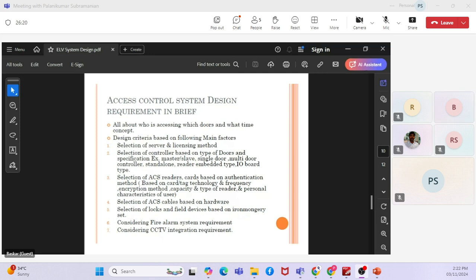So when we are choosing the access control system, there are different selection criteria to be taken care of. When we talk about selection of the server, as I mentioned earlier, it is based on whether a failover server is required or a single server is sufficient. We need to check the specification and comply with it. And the licensing method also is based on the readers. We have multiple access card readers, and based on that the licensing differs. So we have to choose the licensing based on the total number of readers. The licensing comes in 64 door readers, 32 door readers, and so on, so the prices differ for each type. Choosing the correct licensing matters, because the value will vary depending on that.